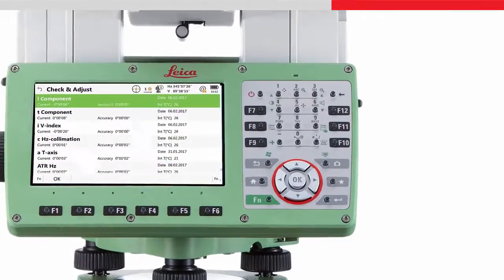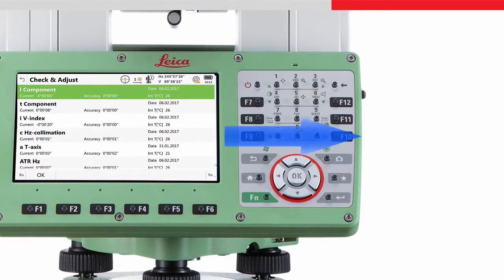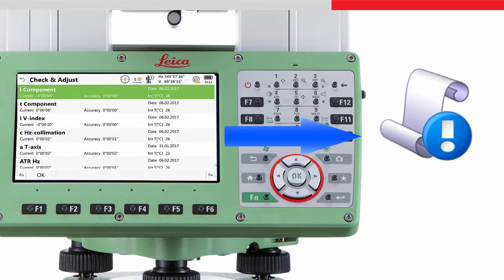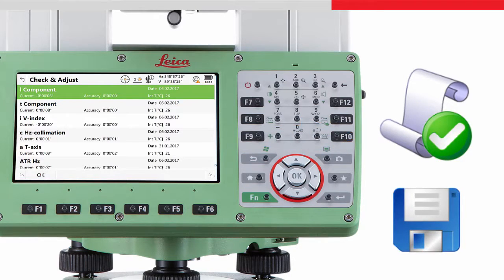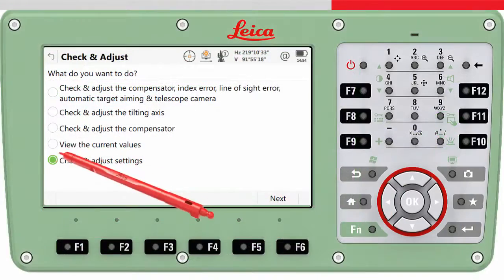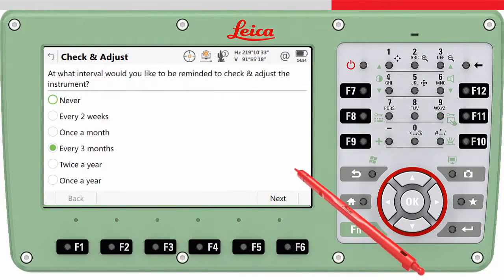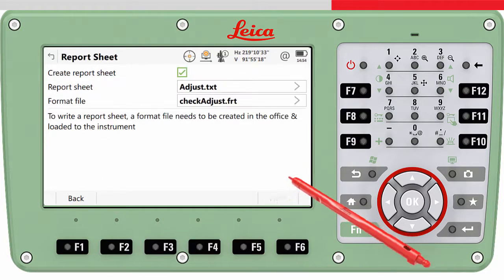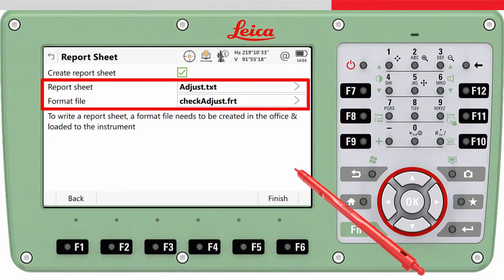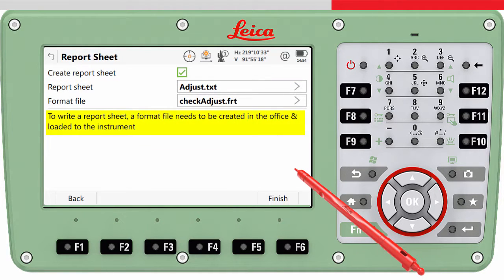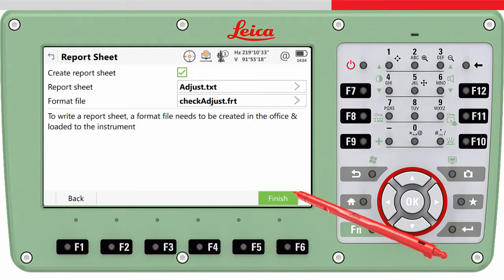Additionally, it is possible to create a report after every calibration to have the calibration values documented, for example, for quality assurance purposes. To create the report, enter the check and adjust settings and then press next. Choose an output file name and select an appropriate format file. The format file has to be loaded onto the instrument in advance. To confirm the settings, press finish.